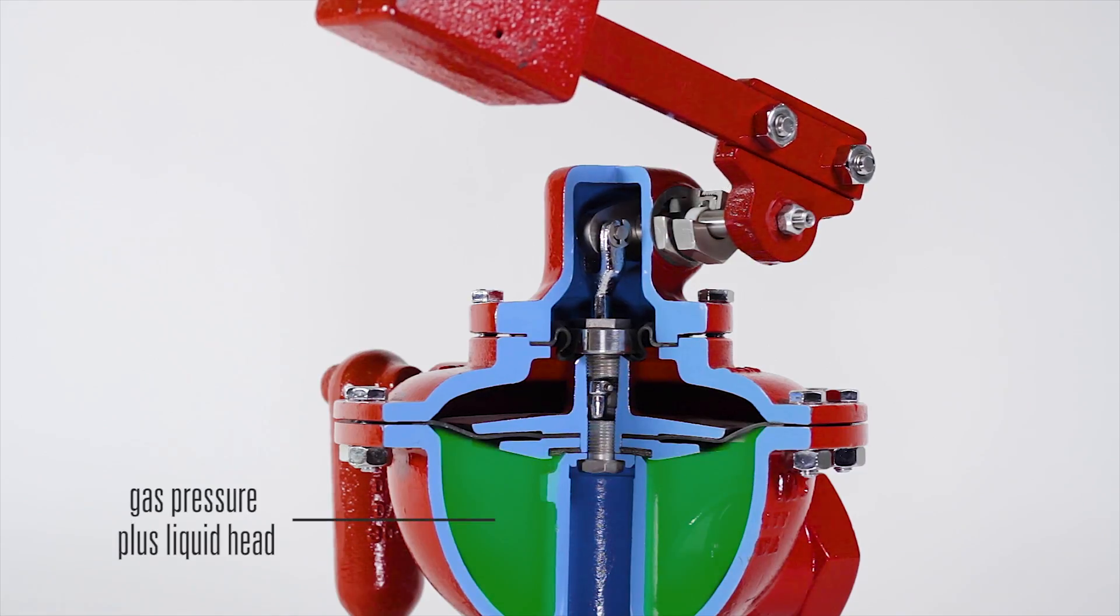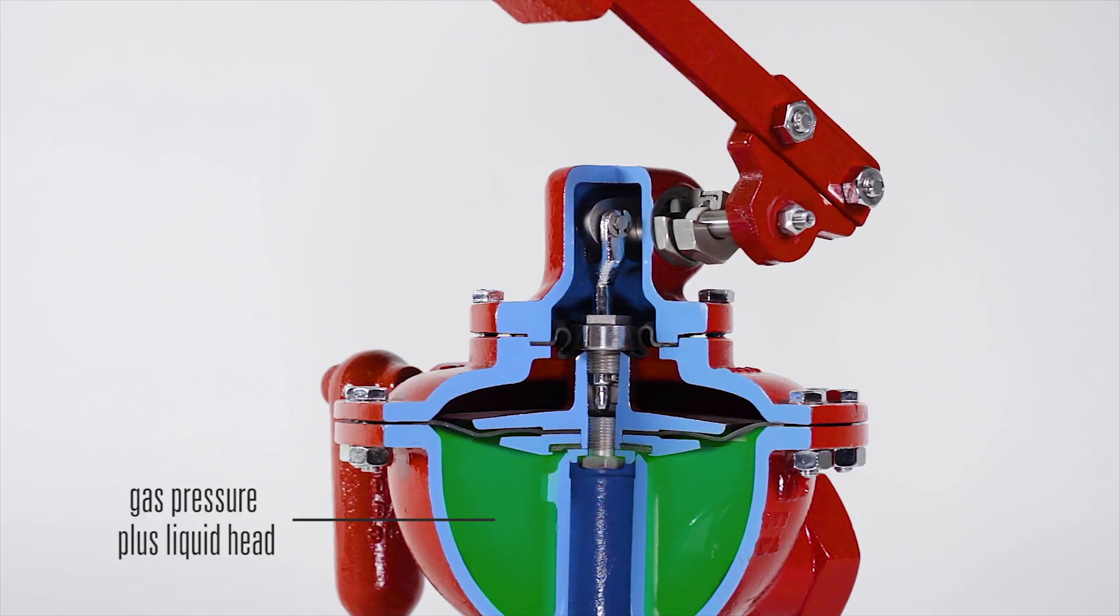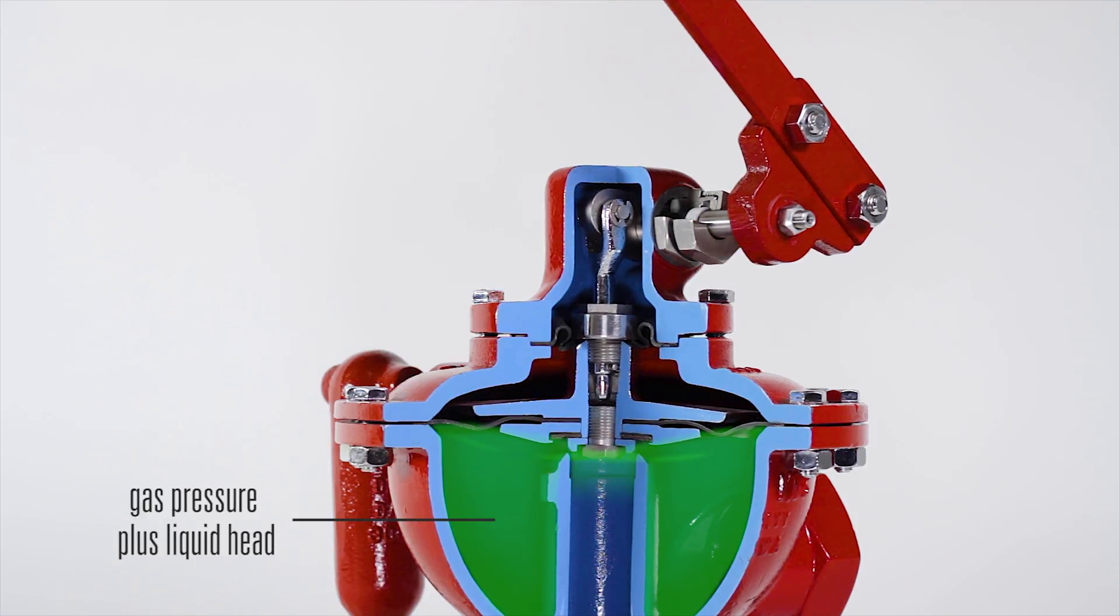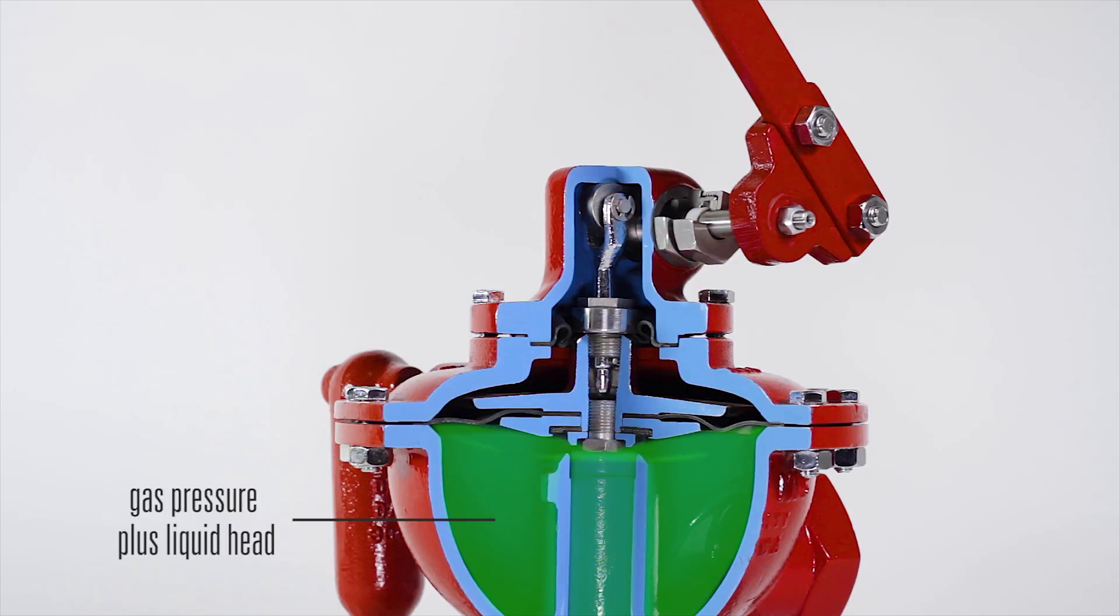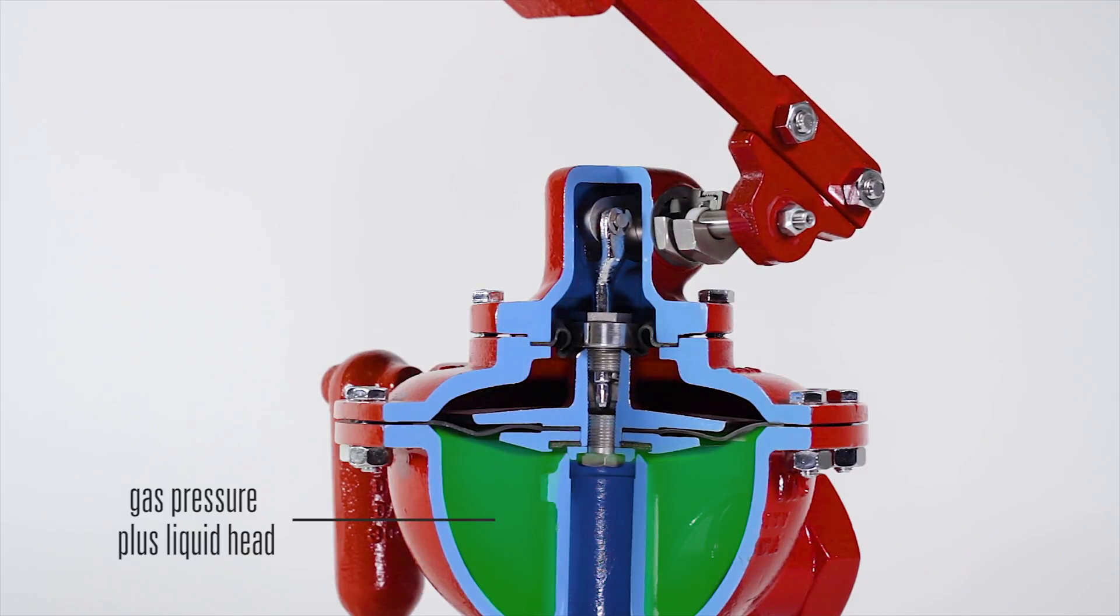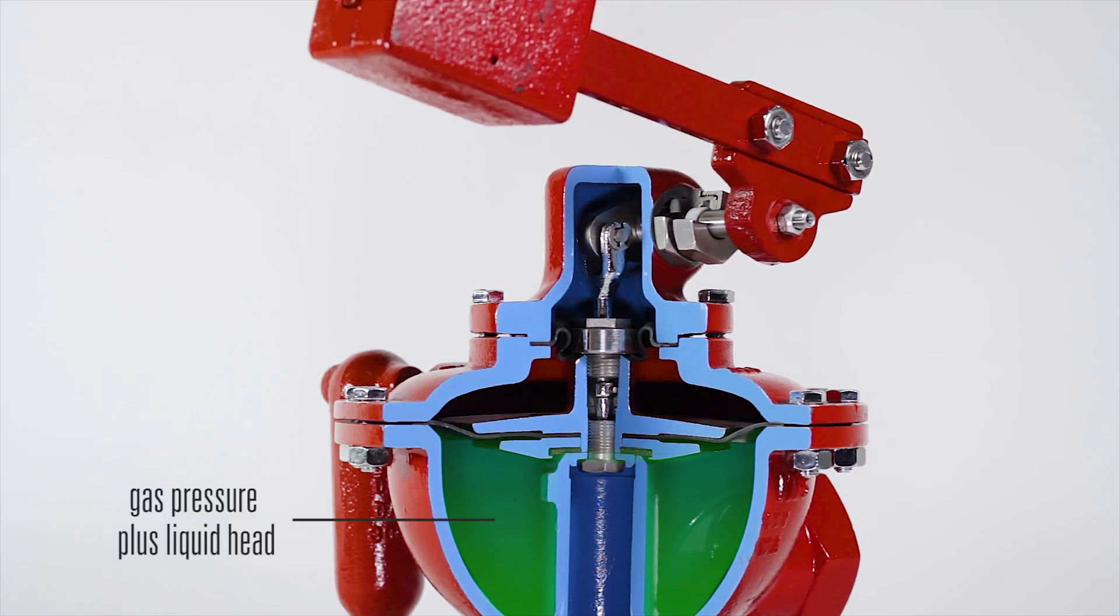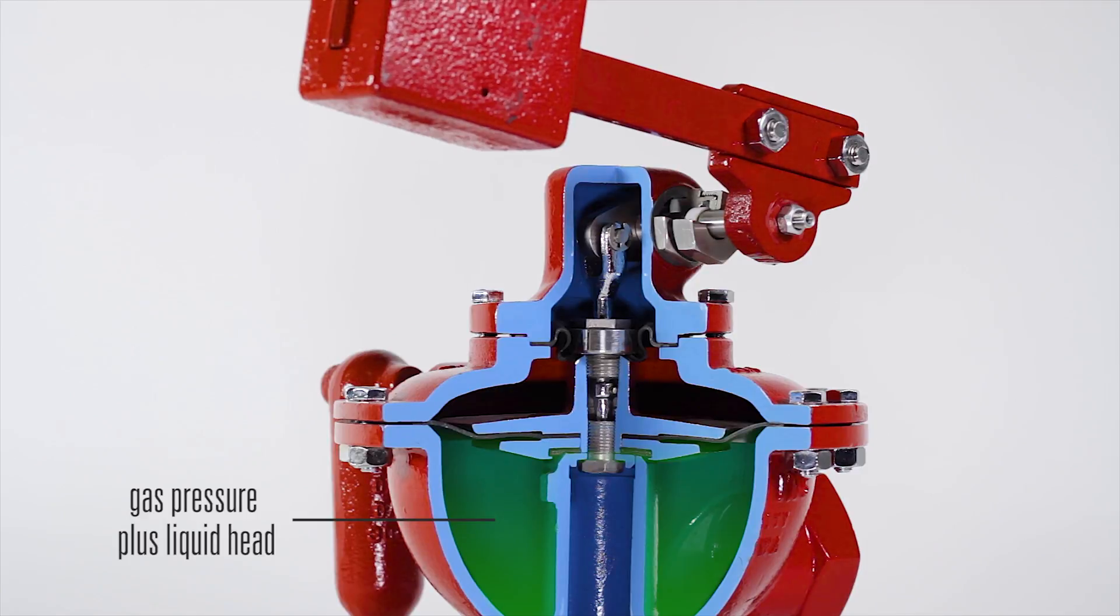When the liquid rises above the set level, it overcomes the force of the weight and lifts the diaphragm assembly against the weight load to open the valve. As liquid is discharged to lower the level, the weight closes the valve.